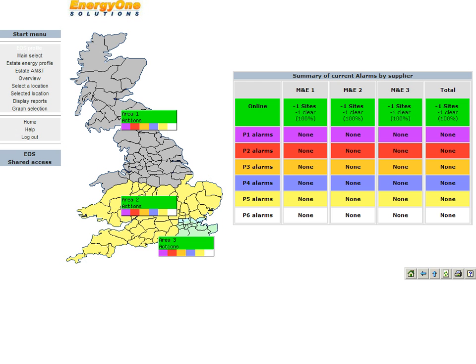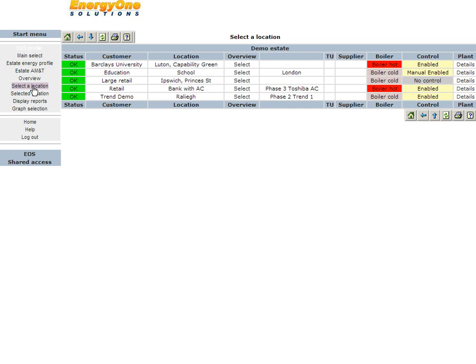This window shows a snapshot of the properties and their current alert status. It also shows the plant and control status. It can quickly be seen on the left that all sites are okay, with no alerts running. The boiler plant can be seen to be either hot or cold, and the control system is set either to run enabled or manual or no control if service work is being carried out.